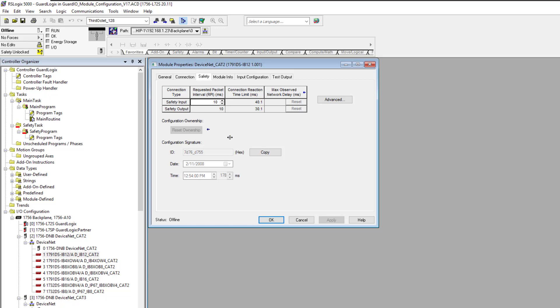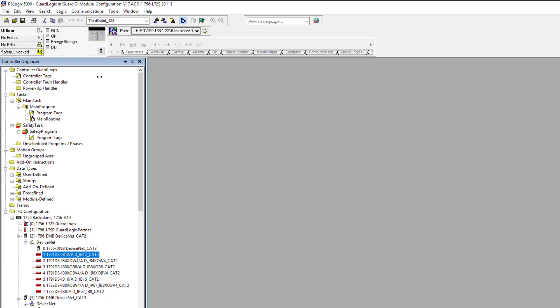Straight out of box, the PLC processor is not going to know that it owns that actual IO, so it can't control that IO until it's actually owned by that IO. Please understand that you have to go, when you're changing safety components out, like in this instance I'm describing, a remote IO, a remote processor, or a local IO, you need to go into that safety tab, reset the ownership, and then that establishes communication. Everything is good. You should start getting green lights. Everything should start functioning properly. You should be able to reset your system and then go from there.